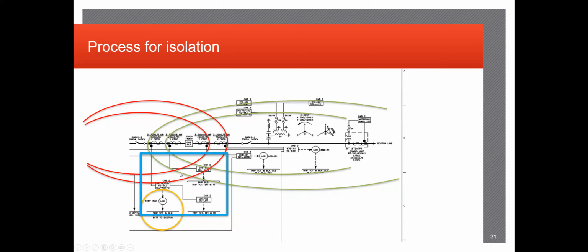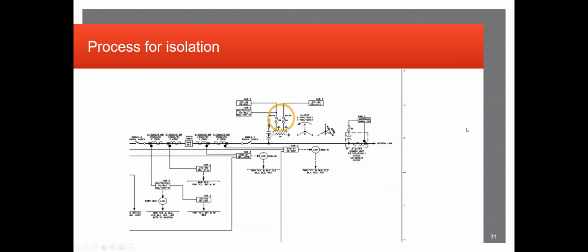And then after all that was done, and we went through our proper isolation steps for isolating the relays themselves, which I'll get into in a second, then you can pull the fuses to the breaker and remove the relays out of service completely.